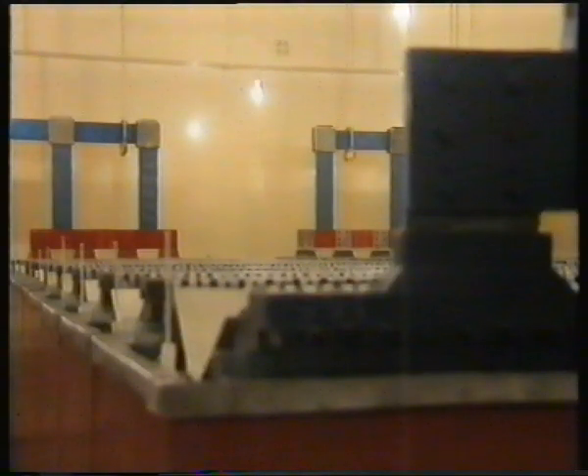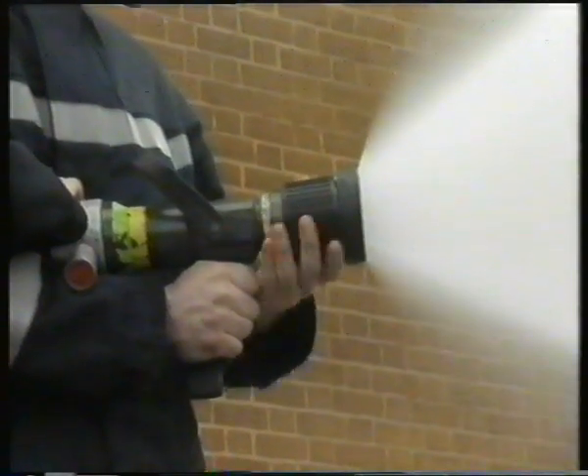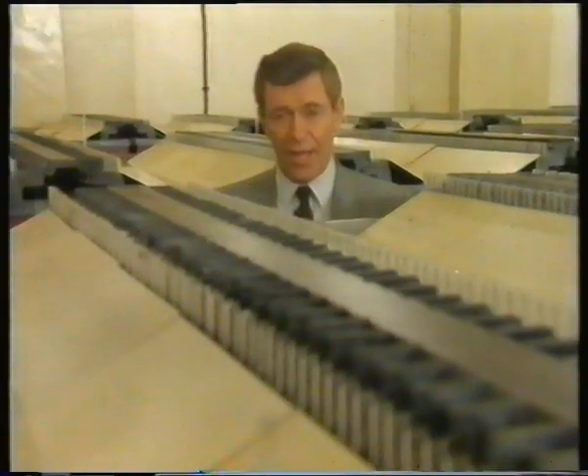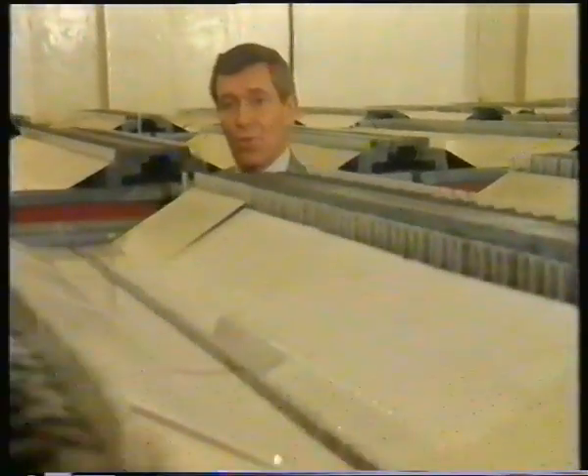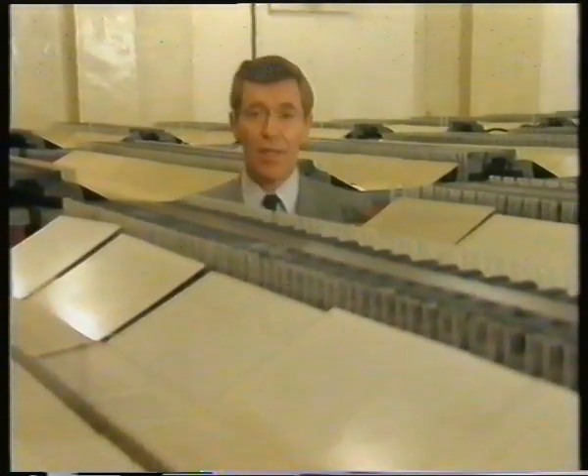If there is a fire here in the battery room itself, spraying the cells with water may produce arcing, but the voltages encountered are small. However, the potential danger from high, short-circuit currents should not be overlooked. The use of a fog nozzle in fighting fires in any energized equipment minimizes the chances of receiving a severe electric shock. If hydrogen gas is present, there is an inherent risk of explosion. Wet cell fires can also create acidic fumes that cause skin and eye irritation. Breathing apparatus may become contaminated in this environment.